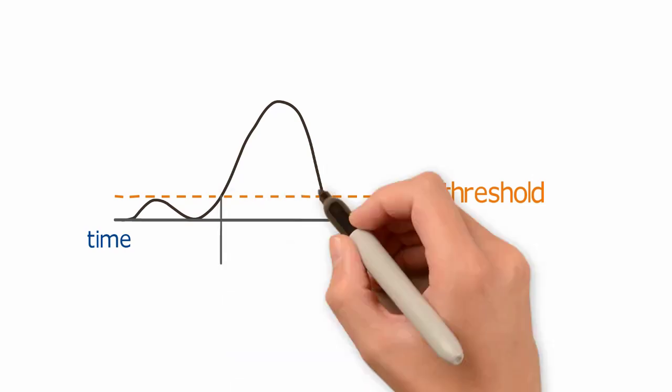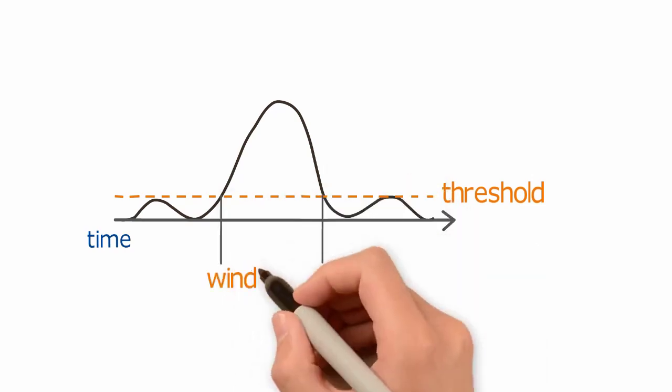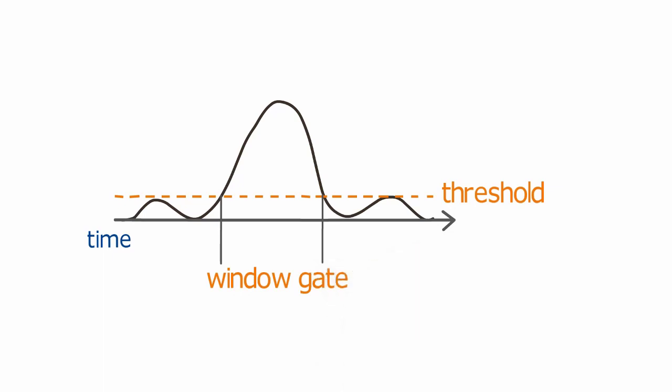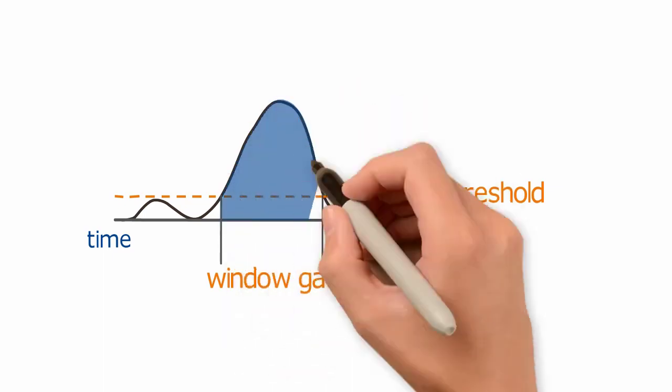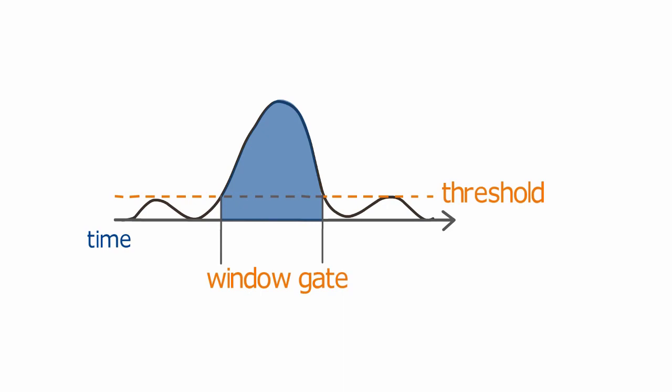The period of time that the pulse is above threshold is the window gate. Any signal measured during this time period makes up the area of the signal. However, a portion of the voltage pulse is below threshold, resulting in an incomplete measurement of the area of that pulse.